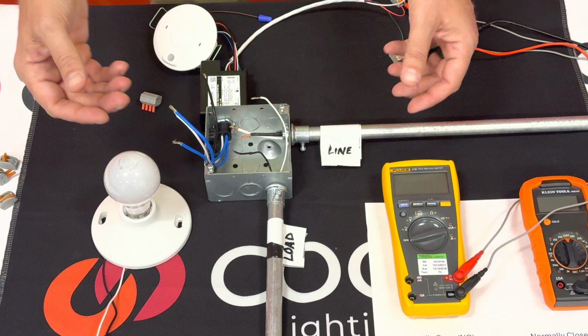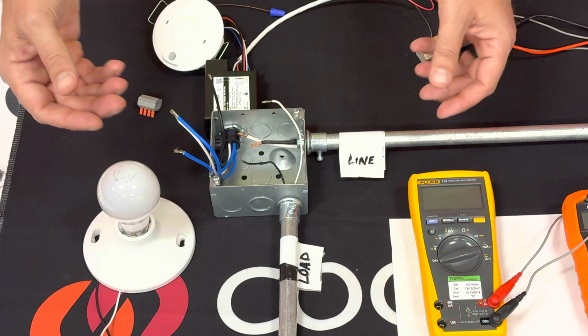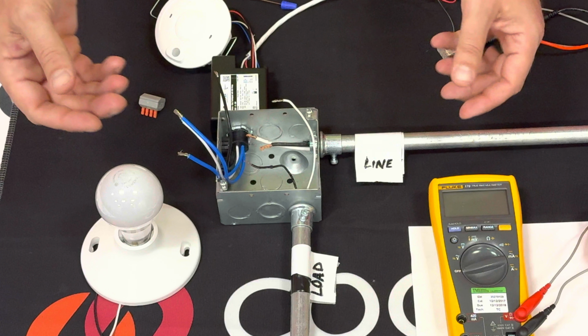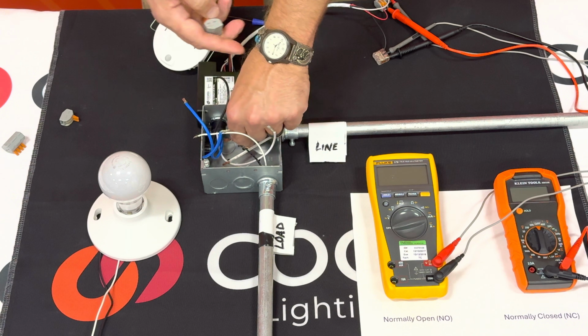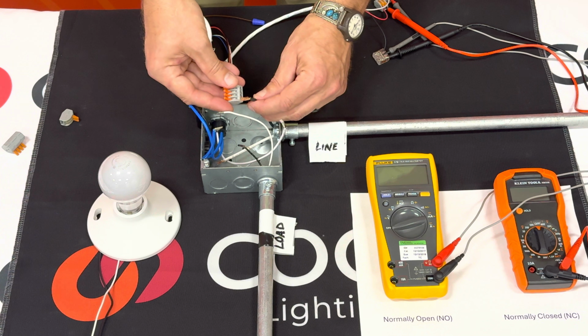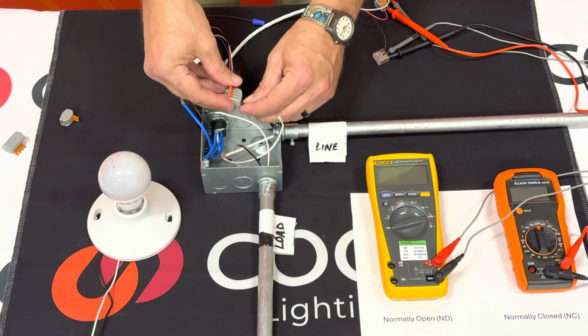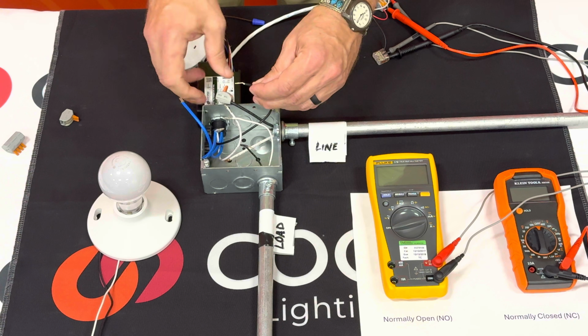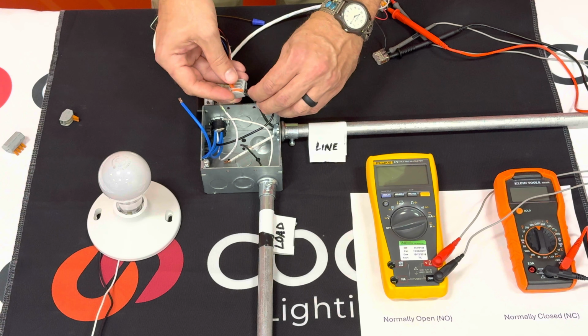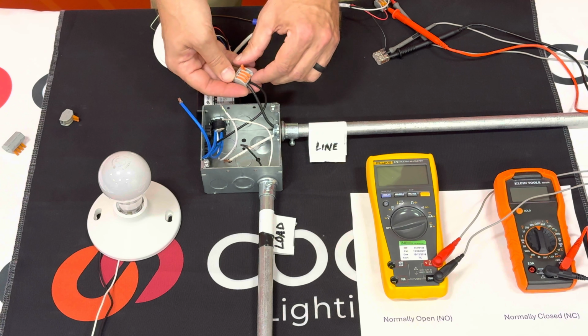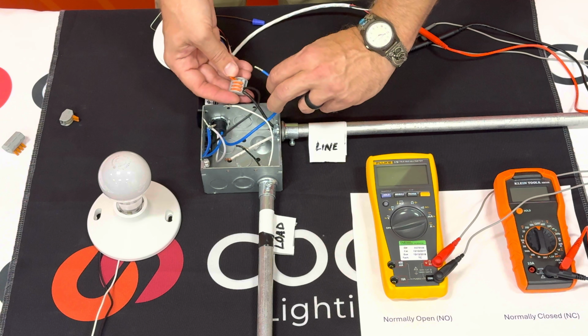RSP-V high voltage wiring. In this first example, the RSP-V will control a load directly. On the line side, there should be a hot and a neutral wire. On the load side, there should be a switched and a neutral wire. First, connect the black line from the source of power with the black line from the RSP-V and one of the blue switched wires from the RSP-V.